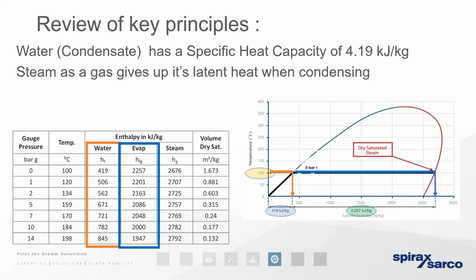And we've also mentioned previously that we know that steam carries this combination of the latent heat and the sensible heat. We refer to that as the total heat. So the total heat is carried towards the process, the heat exchanger, but we know that when that steam condenses, when it gives up its heat energy, it's actually the latent heat, the box in blue, that's the heat energy that travels across the thermal barrier and into the process. So what that actually means is the energy that's left behind in that liquid condensate, well, it's the same as the sensible heat that we put into the water to bring it up to boiling point in the first place.